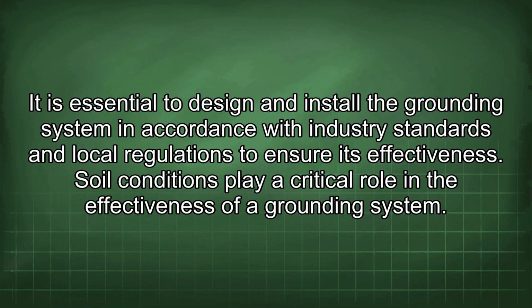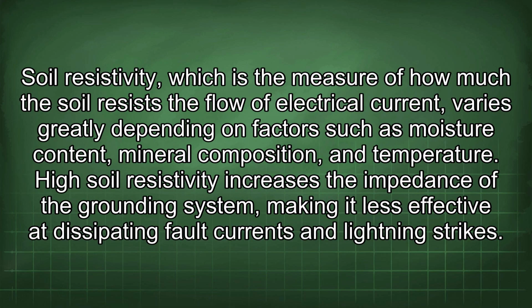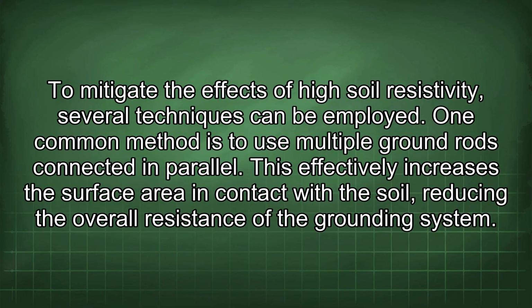its effectiveness. Soil conditions play a critical role in the effectiveness of a grounding system. Soil resistivity, which is the measure of how much the soil resists the flow of electrical current, varies greatly depending on factors such as moisture content, mineral composition, and temperature. High soil resistivity increases the impedance of the grounding system, making it less effective at dissipating fault currents and lightning strikes. To mitigate the effects of high soil resistivity, several techniques can be employed.